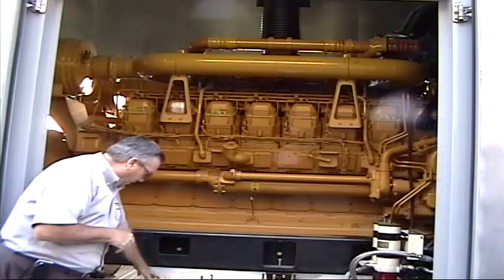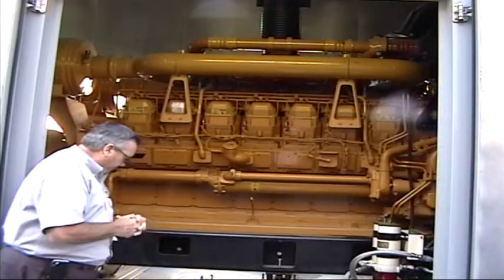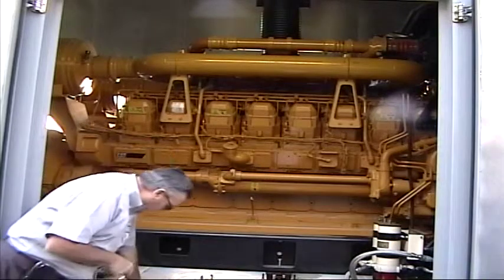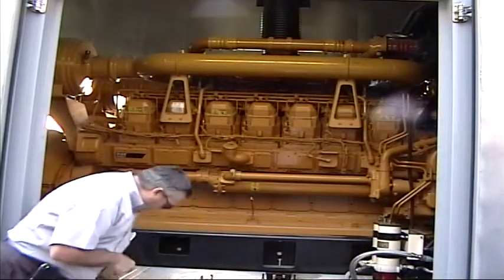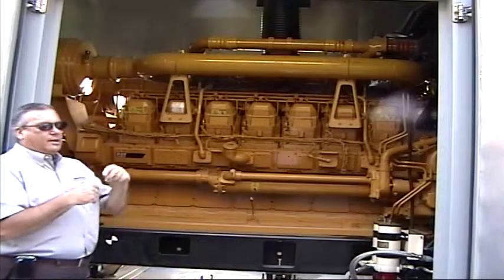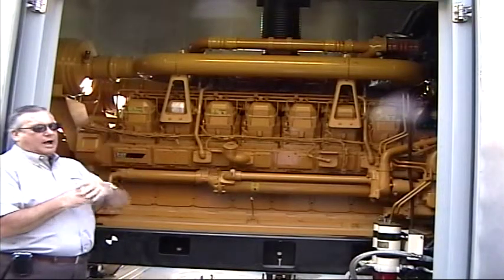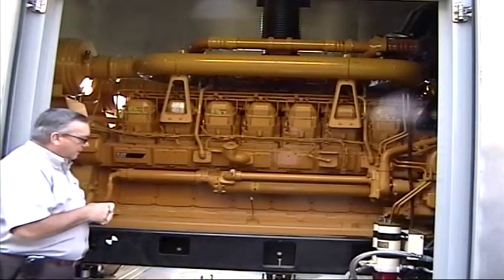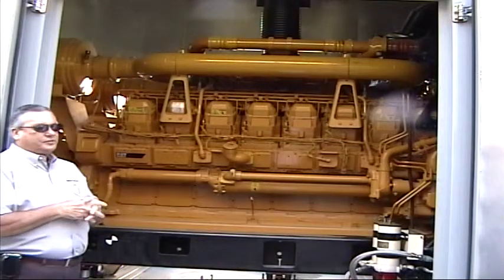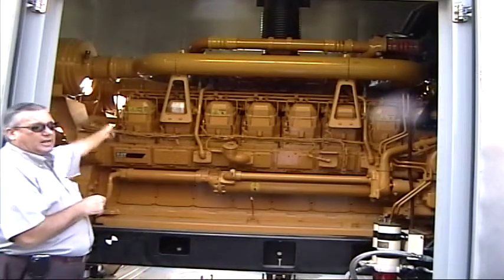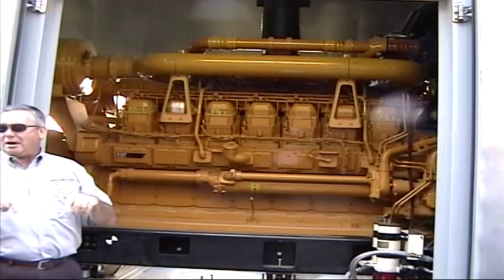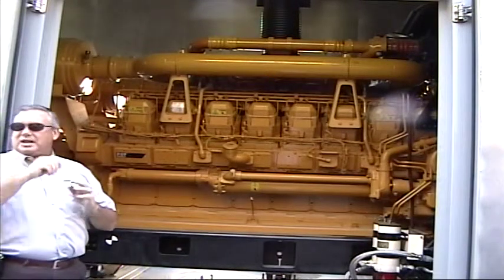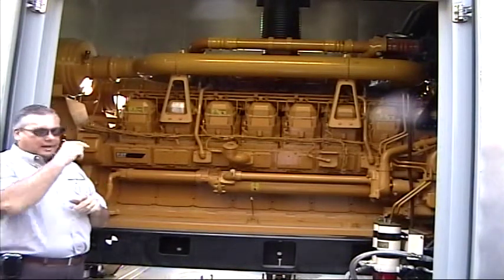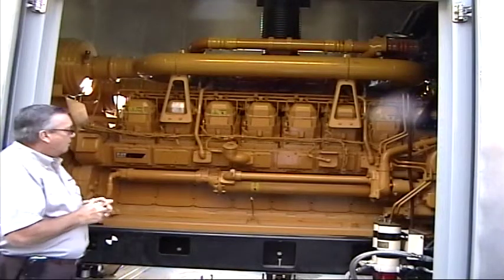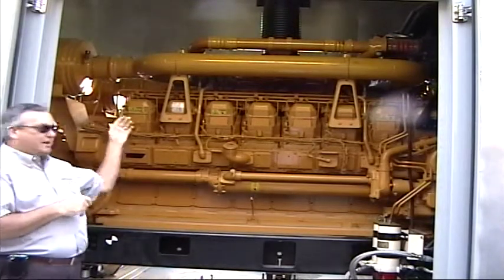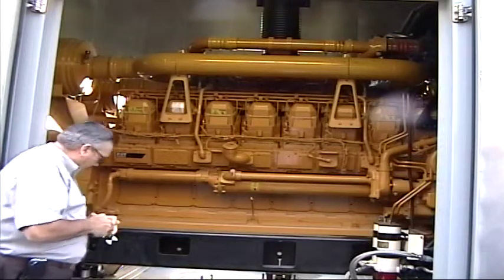Also on this side, you have all the fuel things that go with the fuel system. You have a little pop gauge here that shows we're full, and actually we're so full that we're triggering a high fuel level. It got a little overfilled and we haven't run enough to get it down below that. We'll also see an annunciation on the panel for that right now that's lit. Once that fuel burns down below that level, the switch will open and turn that light off.